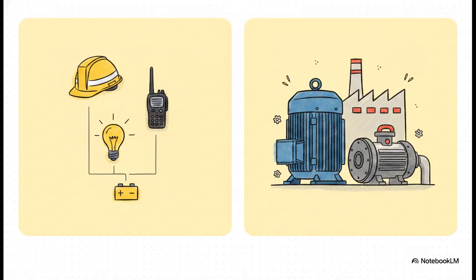Now, when distributing all that power, you've got to differentiate between low-voltage vital loads that keep your personnel alive and high-voltage essential loads required to black start heavy machinery. Vital loads, so think communications, emergency lighting, and navigation, operate at 380 to 415 volts and are basically always backed by UPS battery systems. Essential loads, on the other hand, are your massive 6.6 kilovolt induction motors required for restarting complex LNG refrigeration processes or running your main firewater pumps.